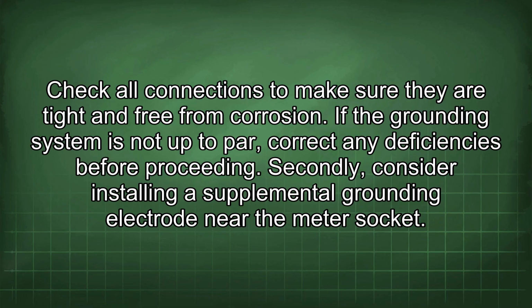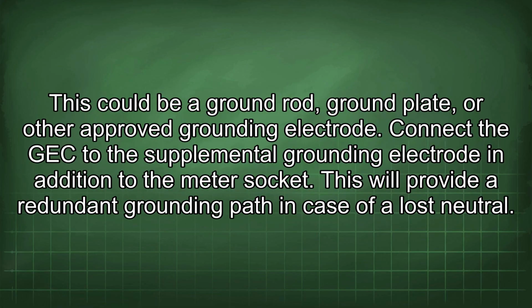Secondly, consider installing a supplemental grounding electrode near the meter socket. This could be a ground rod, ground plate, or other approved grounding electrode. Connect the GEC to the supplemental grounding electrode in addition to the meter socket. This will provide a redundant grounding path in case of a lost neutral.